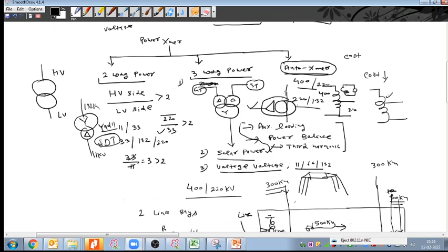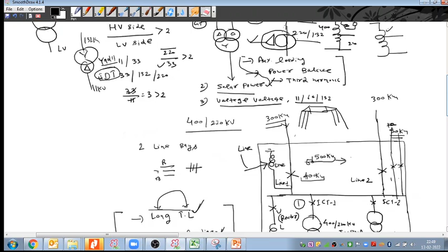Hi, sir. While discussing the auto transformer, we were talking about the tertiary winding, and we added that the tertiary winding eliminates the third harmonic and gives EMF balancing. How does that happen? I will explain with the help of ETAP how it happens. In the tertiary winding, we always connect the delta configuration. So whatever harmonics are coming will circulate inside this tertiary winding. It will not go out of this winding, and it will not feed to the source or to the load. That is why it eliminates the third harmonic or multiples of the third harmonic. It is rotated here and then finishes, due to the delta connection.